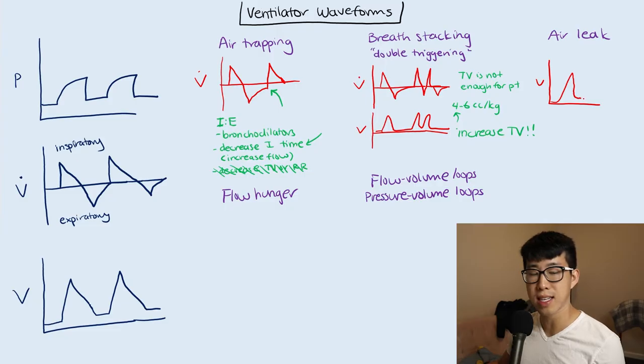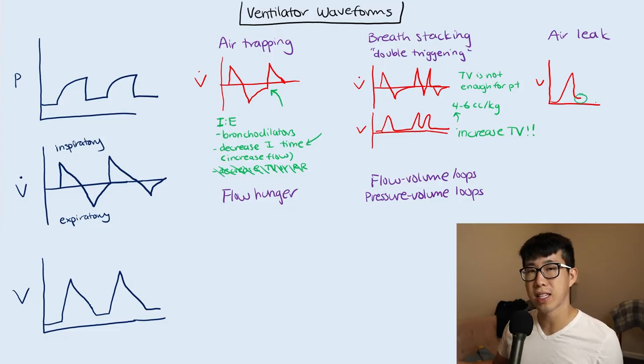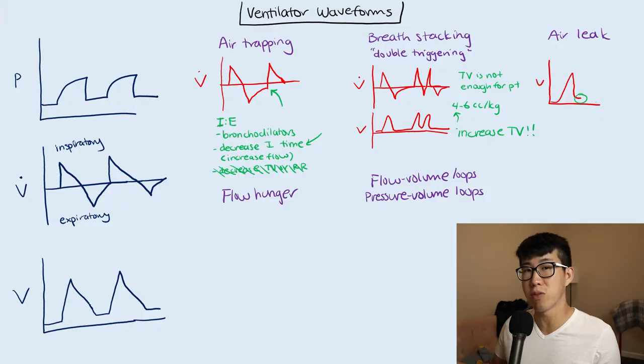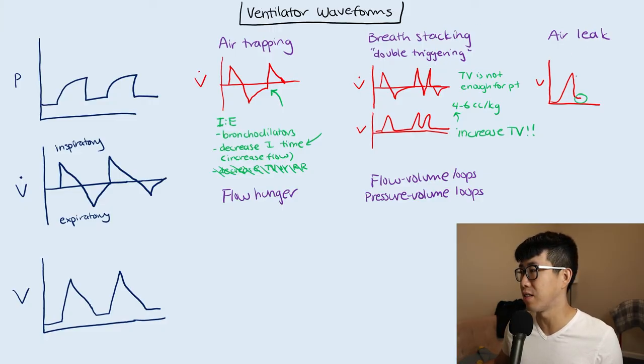Next, let's talk about air leak. This is going to be on your volume curve and you're going to see a normal inspiration, but it doesn't really go all the way to baseline. You have this kind of leak right here where basically the air has disappeared and the machine was not able to calculate that back. You're left with this kind of dead zone right here.